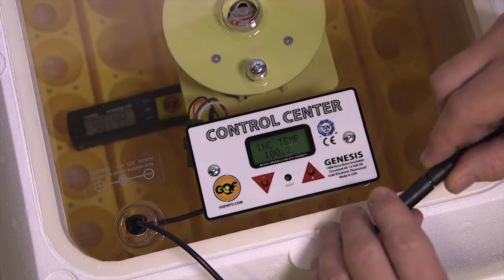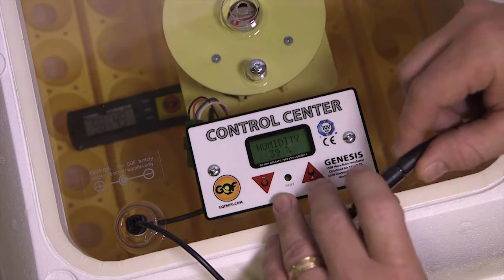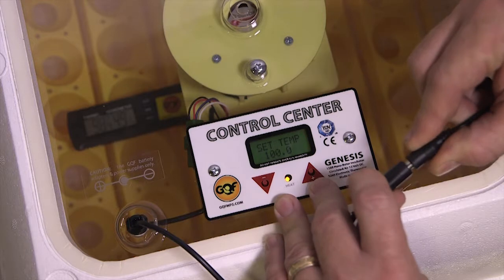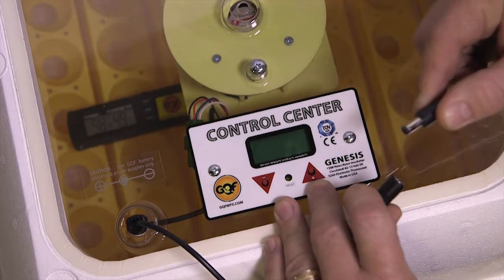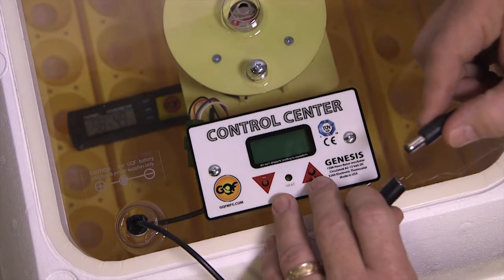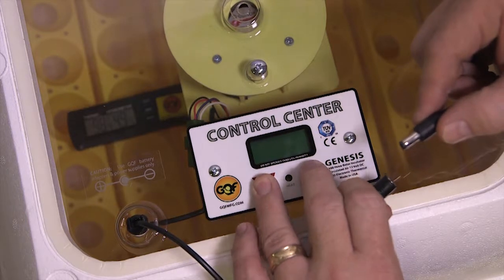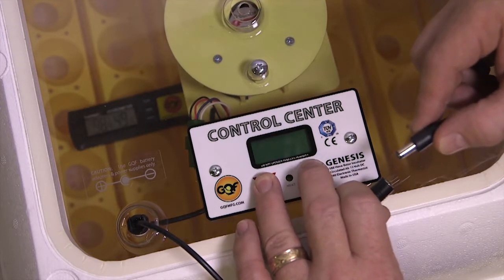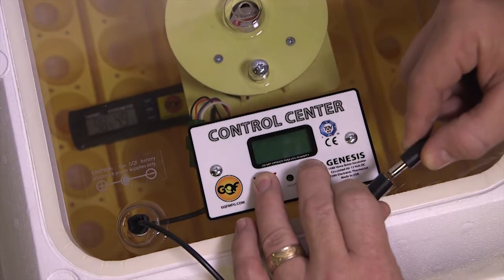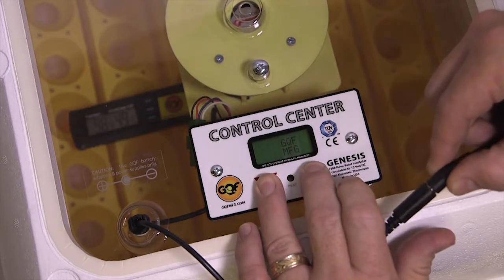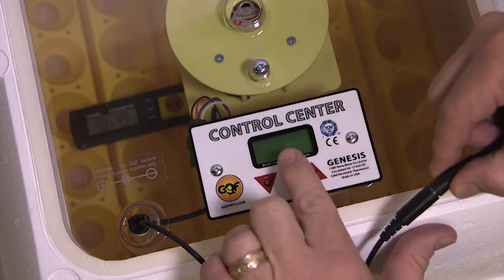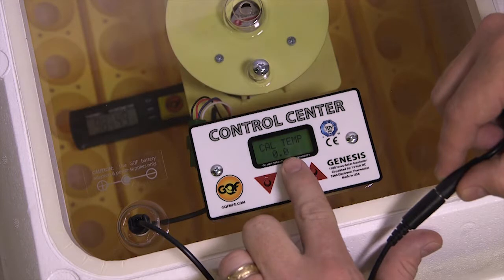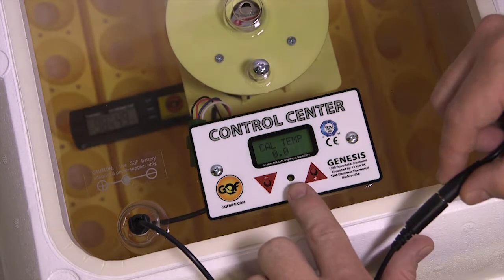And so the first thing you do is you grab the plug and unplug the unit. Just give it a second. And then you want to hold both switches down, push them both. You can kind of feel them click. Hold them both down and plug the incubator back in and keep those buttons held down till that screen goes blank. And you'll see it says cal temp 0.0.